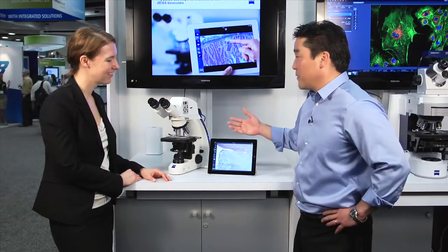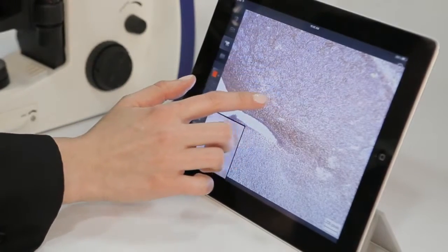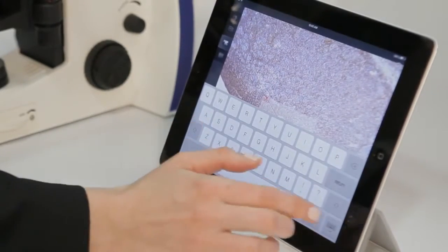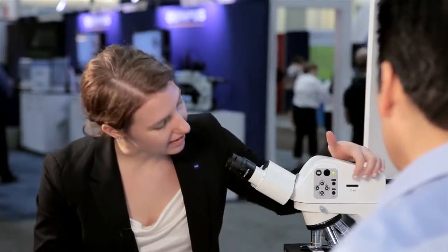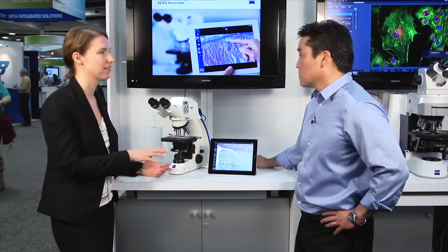The app talks to both the PrimoStar HD as well as our Axiocam ERC-5S, which is one of our new cameras that you can use on any Zeiss microscope. It can take images, it can take videos, and you can also do annotations — you can add pointer arrows, put text on the images, and save the images directly to your tablet. You can put it onto the SD card, share it with the network, or email the images. All of the images retain the metadata, which means that if you pull the image up later it saves all the information on the settings that were used to acquire that image, so you can replicate the experiment later on.